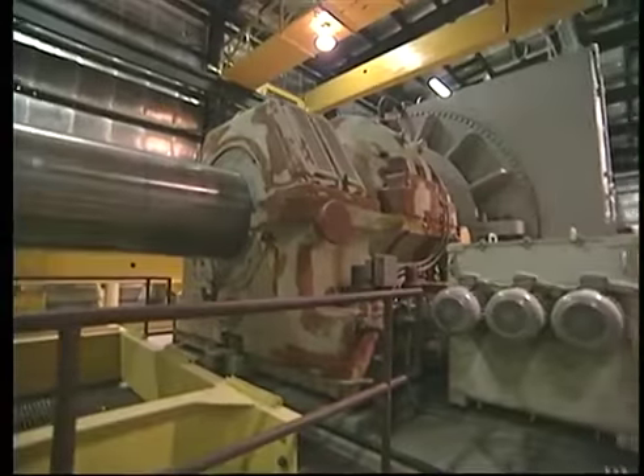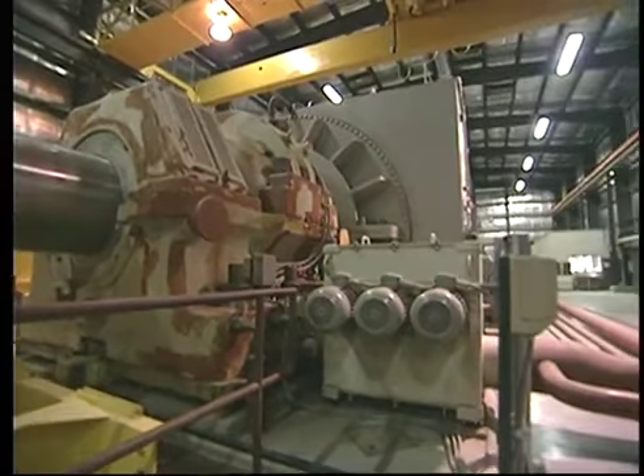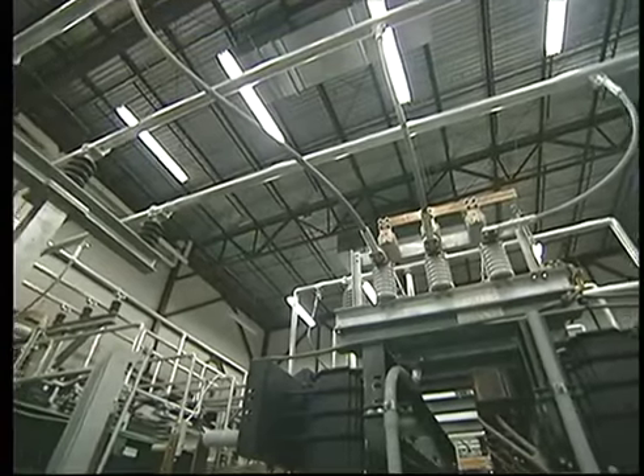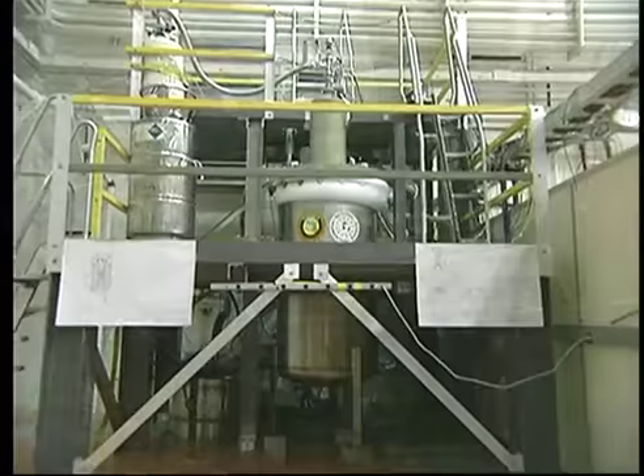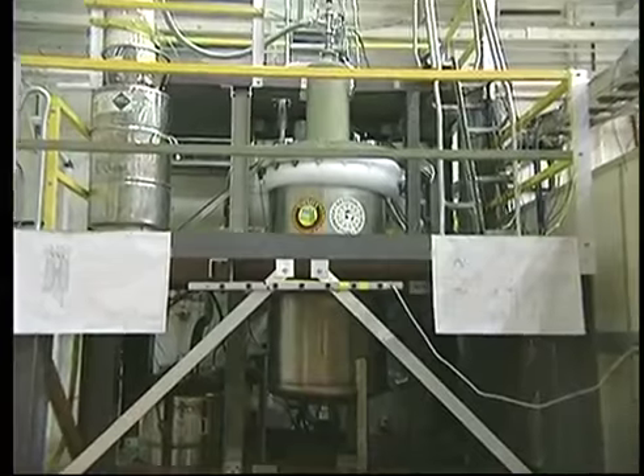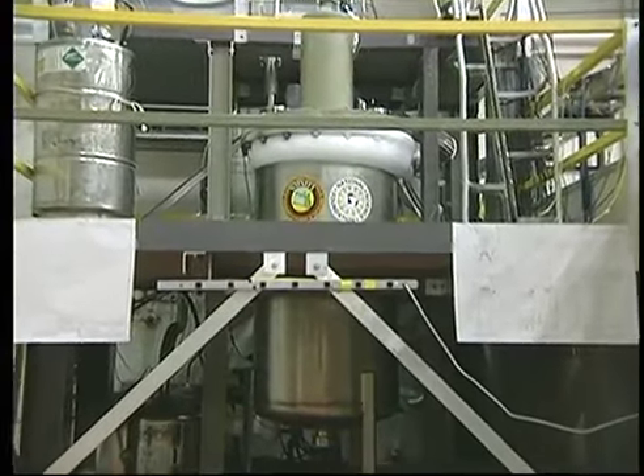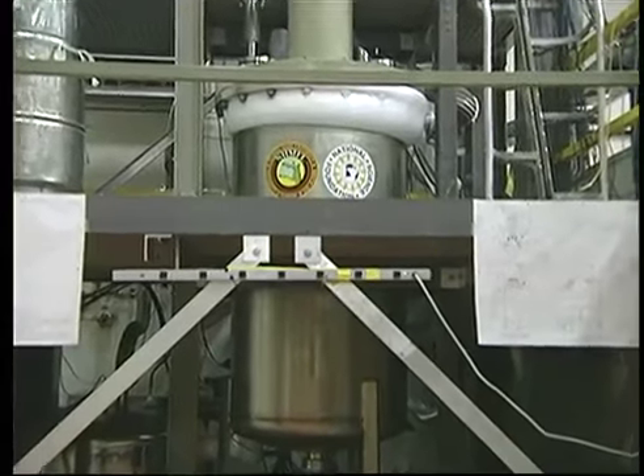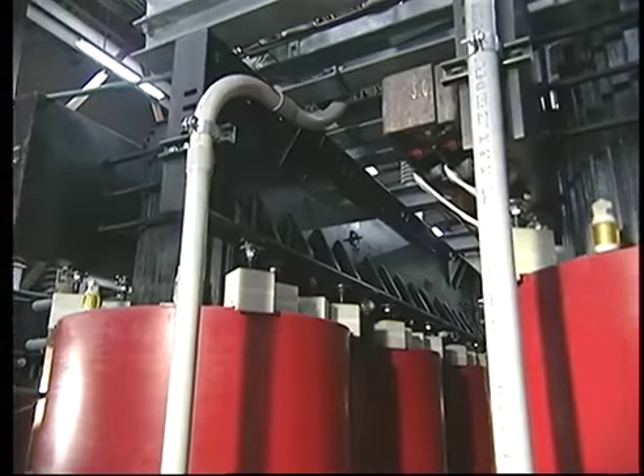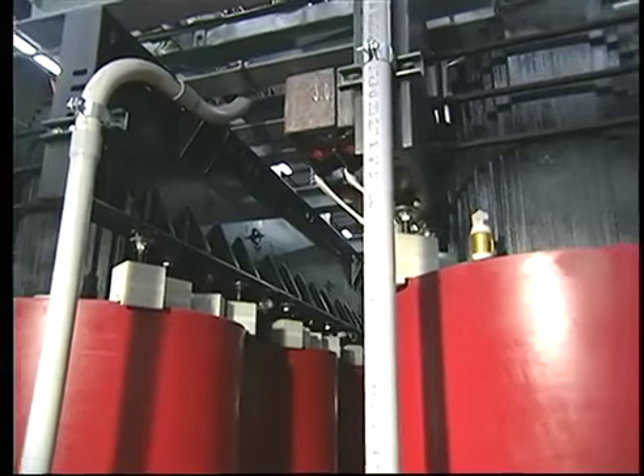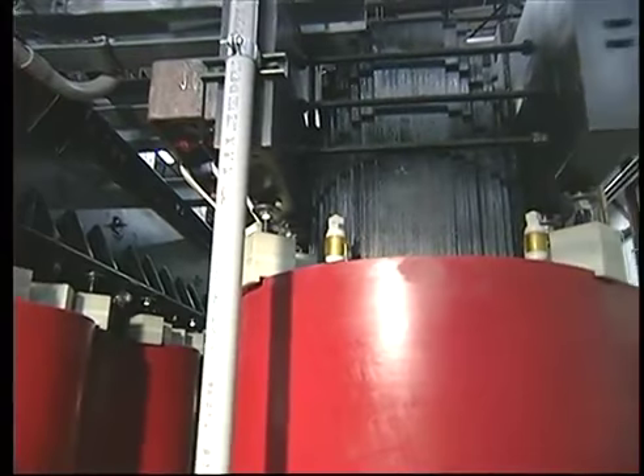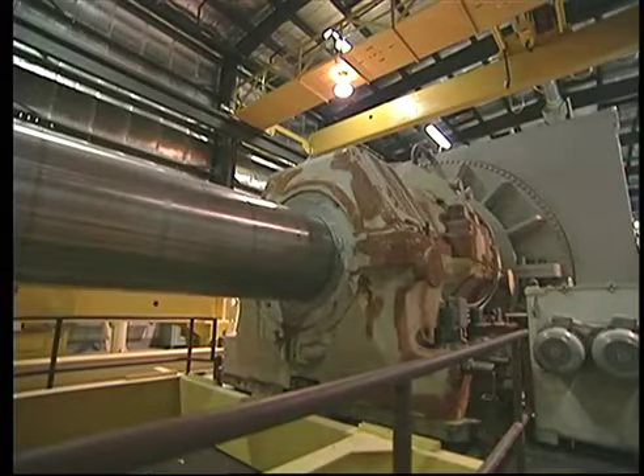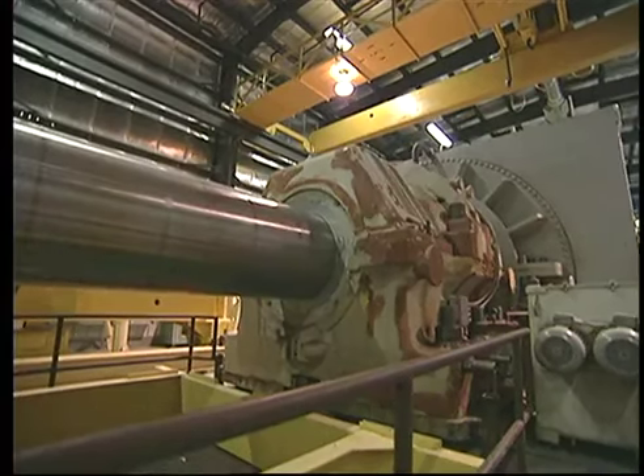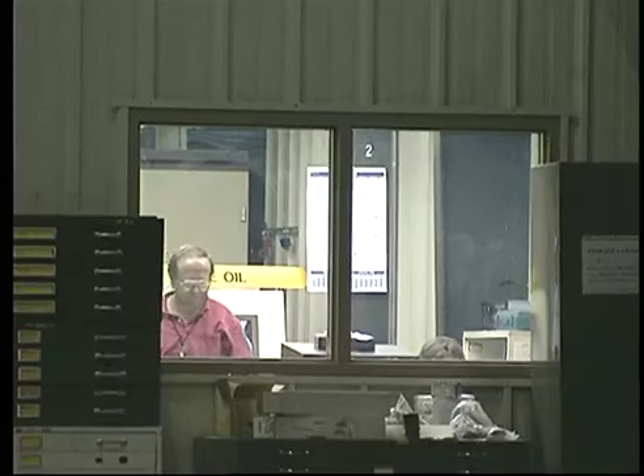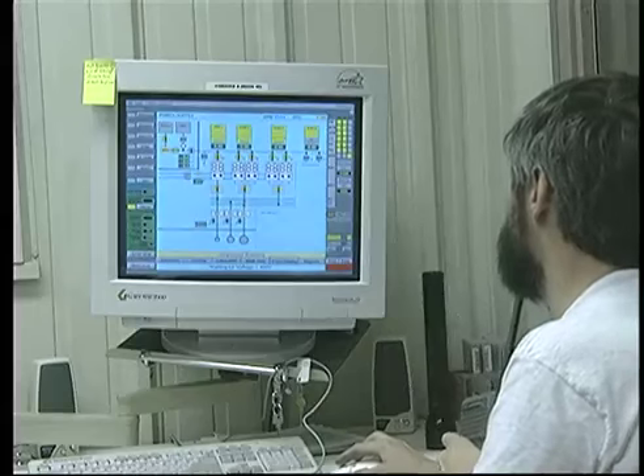For about 2 seconds, a pulse of electrical energy flows from the generator through the conditioning array into the magnet. About 30% of the 90 megajoules delivered to the magnet is recovered and returned to the motor generator by operating the power conditioners in reverse. This electrical energy is converted back into the kinetic energy of the rotating shaft, available for the next pulse. Interactions of this energy flowing through the system components produce unique sounds.